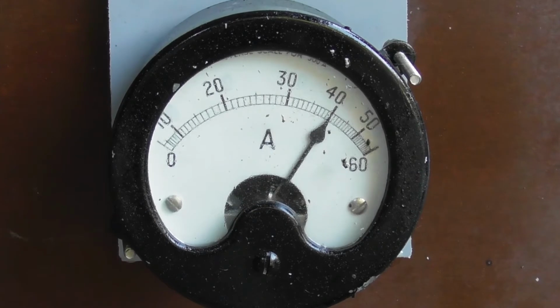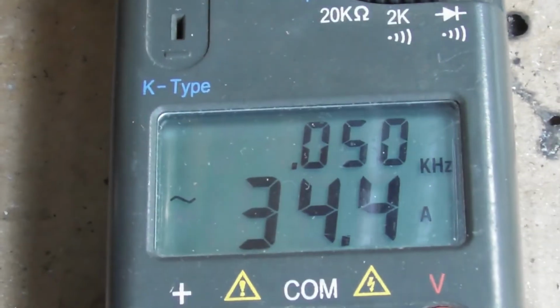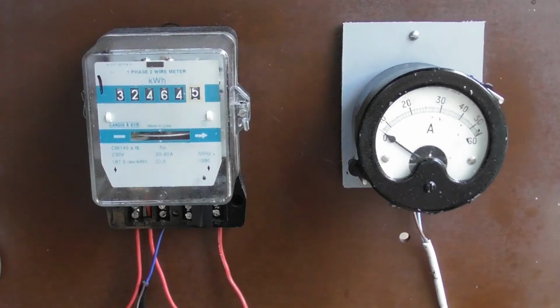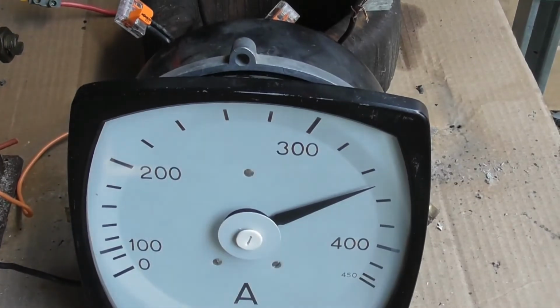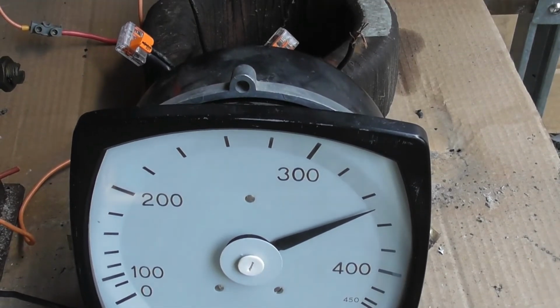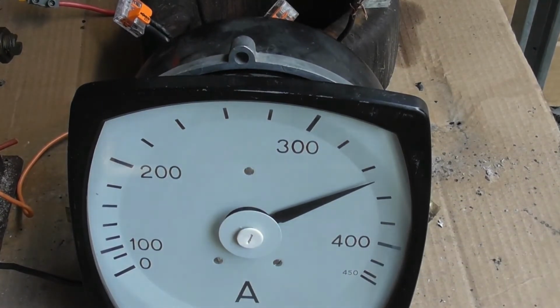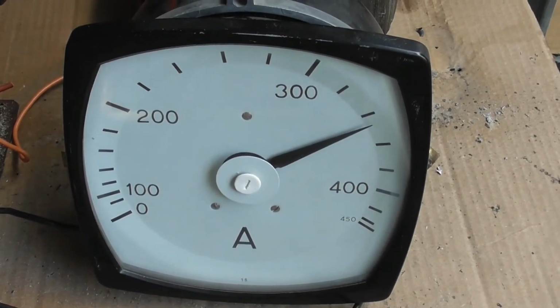Meter is overreading a little bit. It's 40 ampere on this meter, and my multimeter, although it's not super accurate, is 34 ampere. So out a bit, and I'll show you what I'm doing. So that meter sits now at 40 ampere, while this meter here sits at about 350. So I'm gonna reduce the amount of turns I put on this current transformer, it's a 1 amp current transformer which I matched up with this meter.